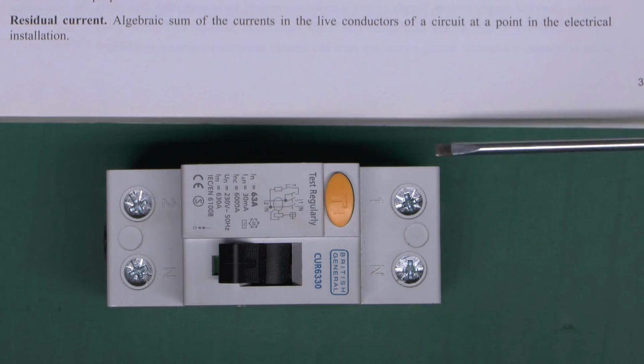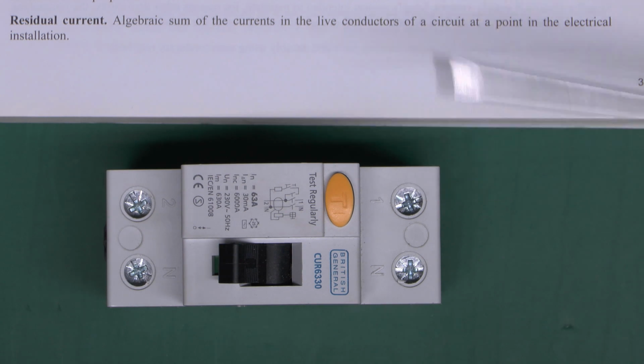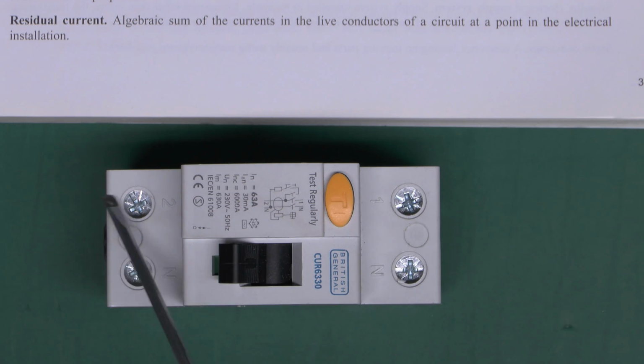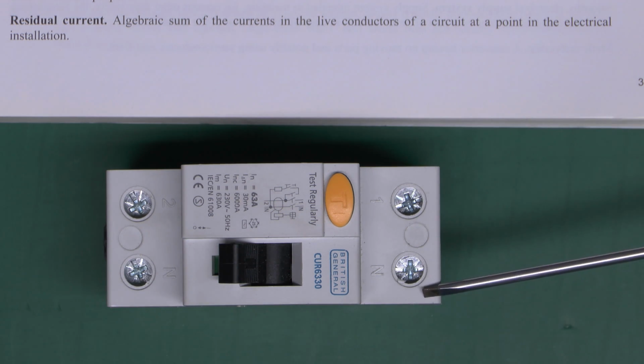Now, in the case of this particular RCD here, we've got the line which comes in here and comes out here, and that will go off to a load or some other device over there. And of course, to complete the circuit, it will come back via the neutral in here, and of course out of here, and that's back to the supply. So if, for example, we had, say, 1 amp coming along into the circuit, of course 1 amp is going to flow through the entire circuit, because obviously that's how circuits operate. But the algebraic sum of those is 1 amp coming in this direction, so we'll call that, say, plus 1 amp. And of course, coming out again, we've got the same current, but it's in the opposite direction, so we can call that minus 1 amp. So of course, plus 1 minus 1 equals 0.